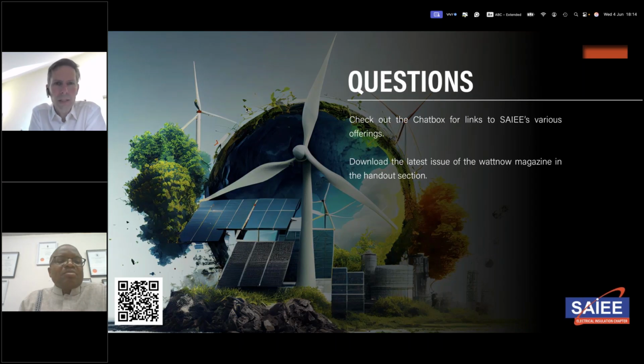It's not biodegradable, I think was the question. In contrast to SF6, which, if dissociated in the arcing into its constituents, sulfur and fluorine, recombines to SF6, this is not the case for the C4. It is dissociated and then converted into other substances upon arcing. But the vendors can dimension the equipment in a way that, with the usual lifetime, like number of switching cycles and so on, there's no allowed deterioration of the gas, and the concentration is below the minimum operational one.